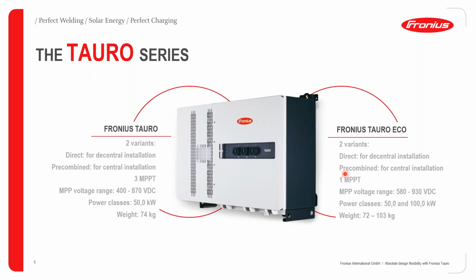For the Tauro Eco, we have one MPP tracker. For the Tauro, we have three. Therefore, we also have a little bit of a difference in the MPP voltage range. It goes from 580 up to 930 volts DC on the Tauro Eco, versus a little bit broader range on the Tauro, from 400 to 870 volts DC.